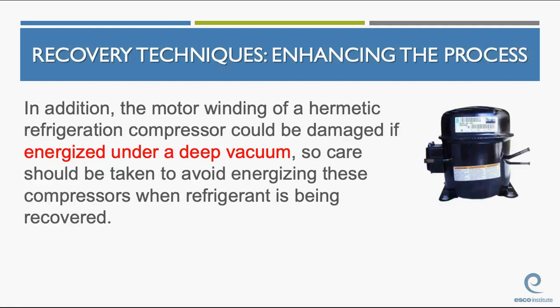In addition, the motor winding of a hermetic refrigeration compressor, and that's air conditioning as well, can be damaged if energized under a deep vacuum. So care should be taken to avoid energizing any compressor in the system when the refrigerant is being recovered. How do we prevent people from energizing compressors in a system when you're recovering the refrigerant? What's the easiest way? Lock it out. Lock it out and tag it out. There's a disconnect near every air conditioning unit. Lock it out.